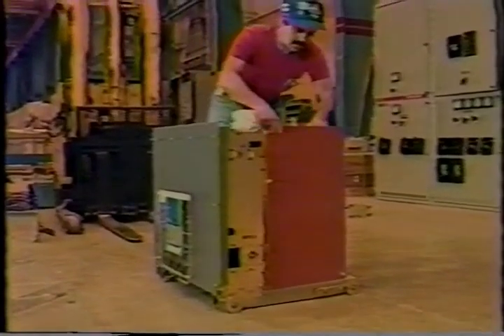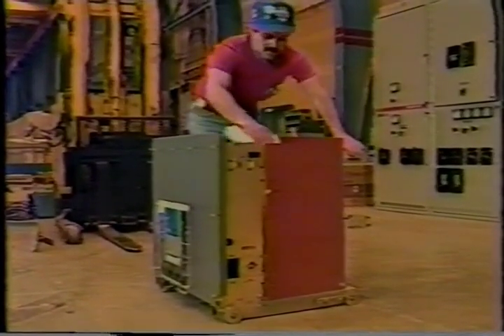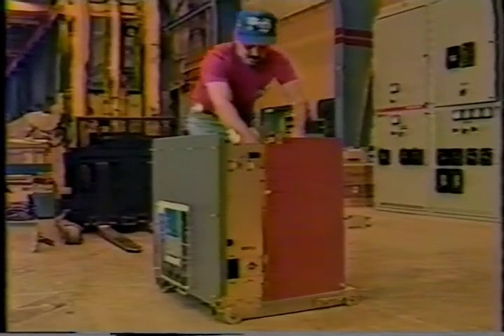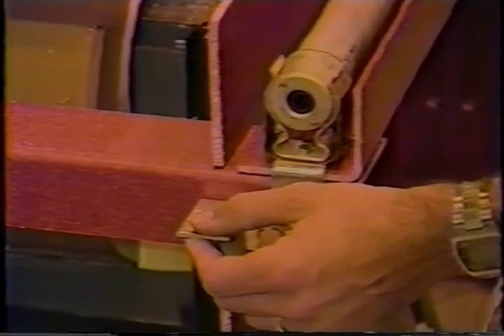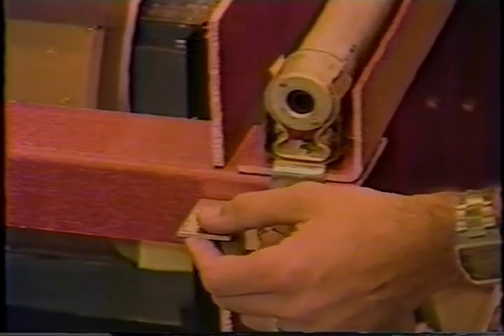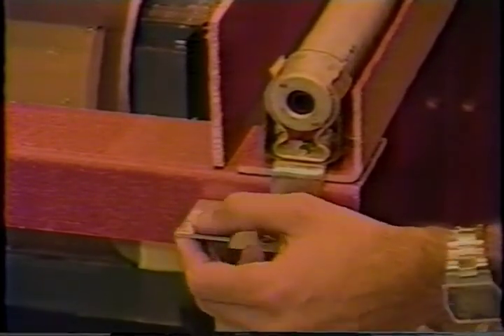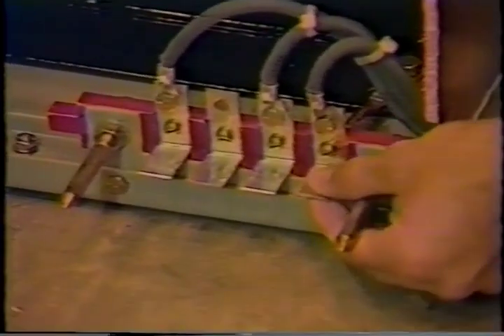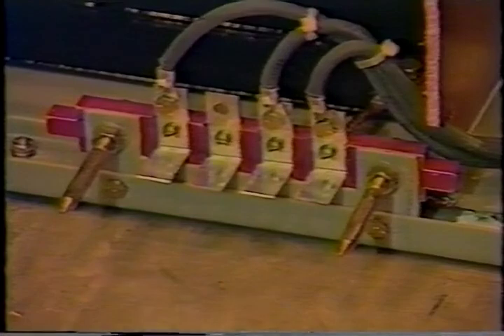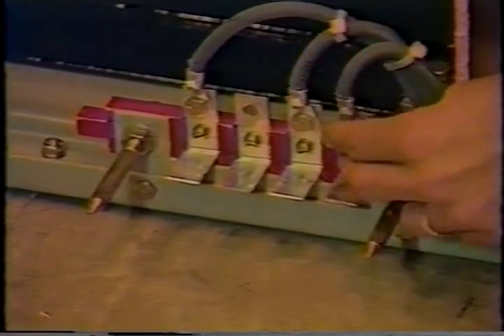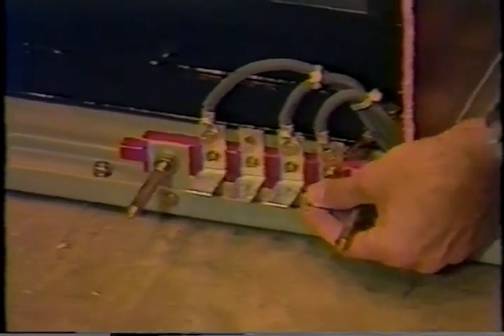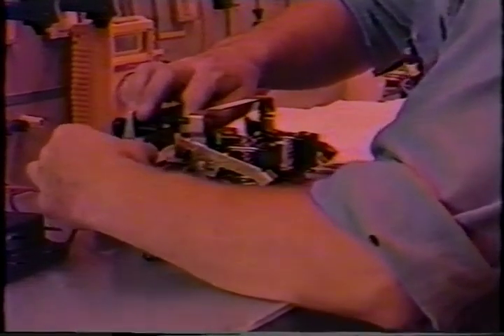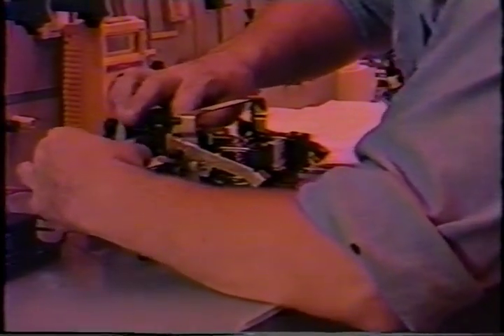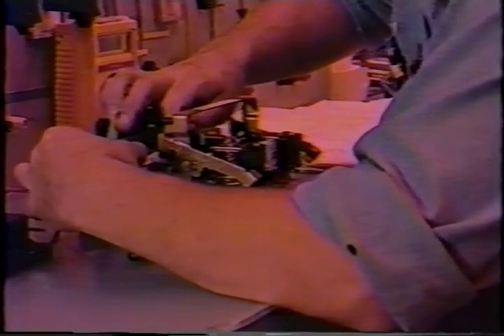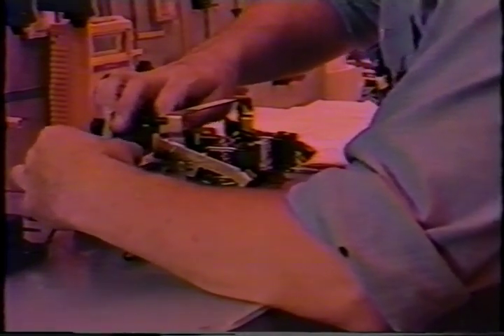Check each breaker while it is out of the housing for all items recommended in the breaker instruction book. Inspect all primary and secondary disconnecting contacts, such as those on draw-out transformers, for abnormal wear, fatigue, or overheating. Replace if necessary. Otherwise, treat the same as the main disconnecting contact shown earlier. Relay contacts should be inspected and dressed or replaced when the surface becomes pitted. Unless repetitive duty has been experienced, little attention should be required.